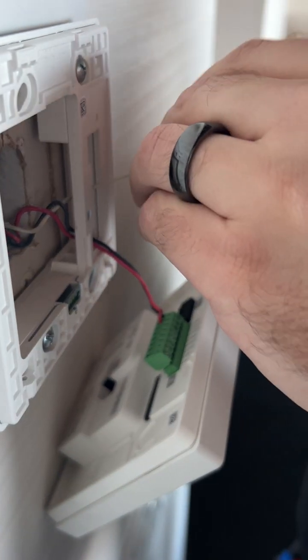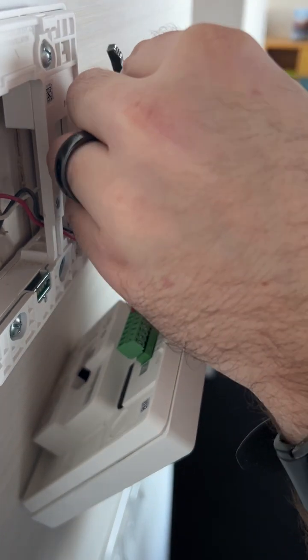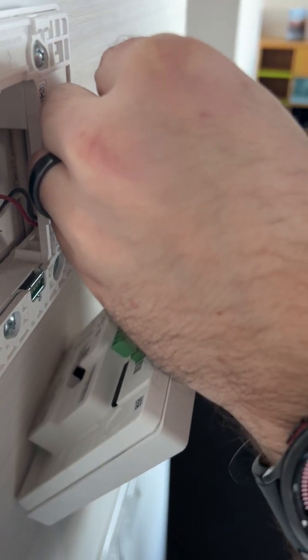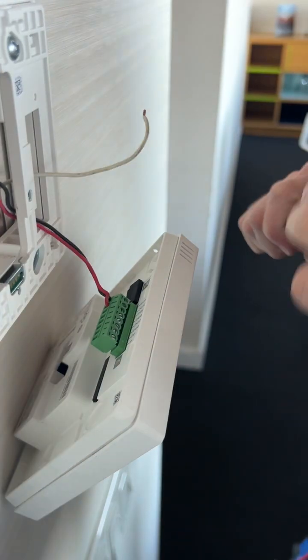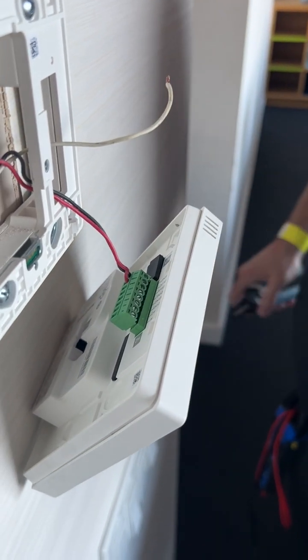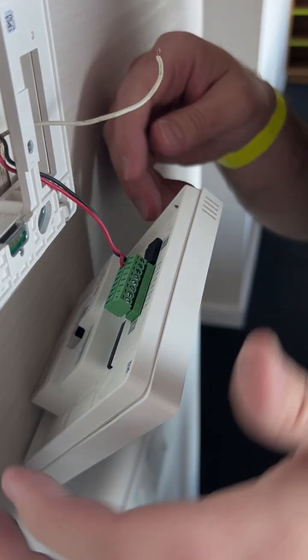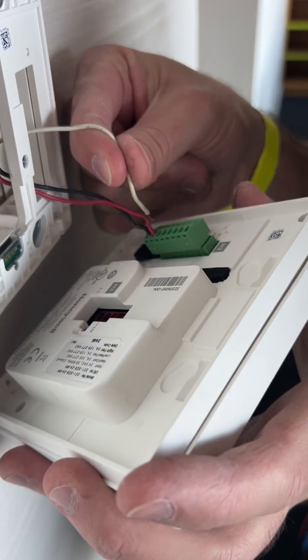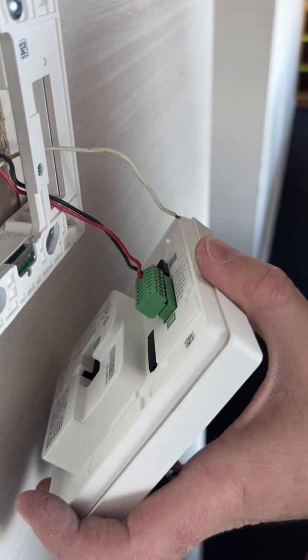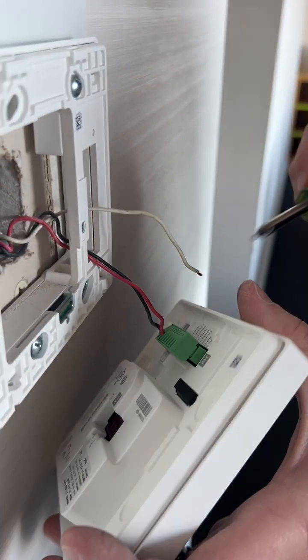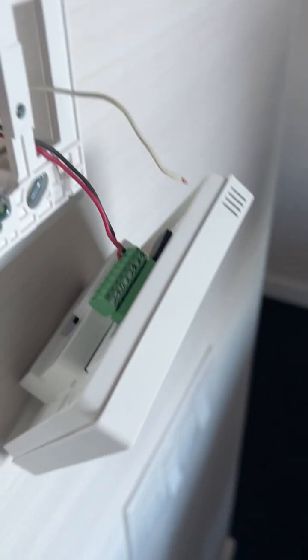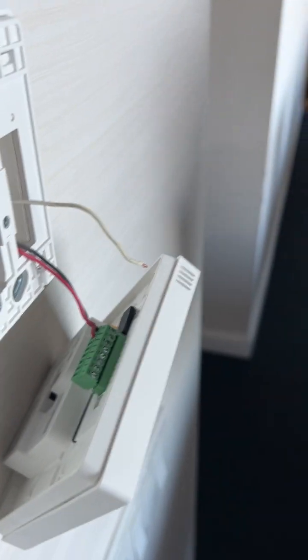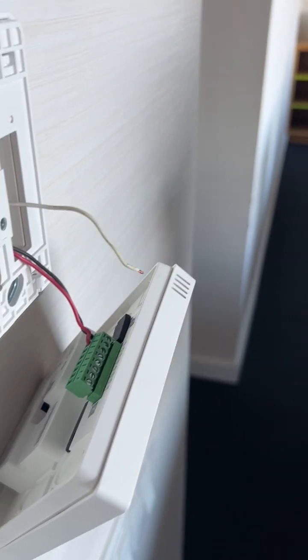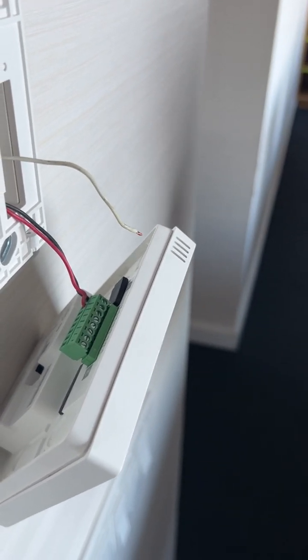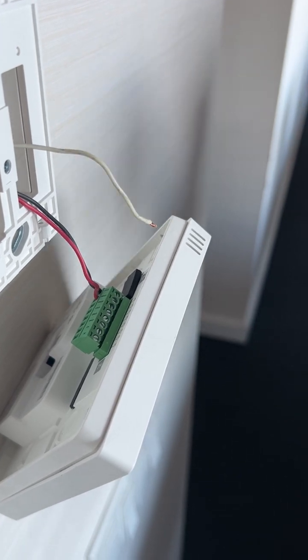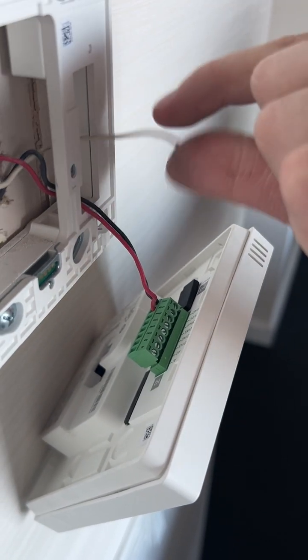Okay. White's communication. Yes. Black is 24 volts, right? And red's common? Or black is common, and red is your 12 volt. Okay. And this is coming from the relay pack, so that's where you're getting the 12 volt power. All right, red 12 volt, black common, and if you're metering it, white, your data communication wire, your S5 bus, will be 4.7 volts DC. All this is DC, by the way. At the thermostat side, what will it be? Like 4.7 to 4.9, from common to your data wire. Got it.